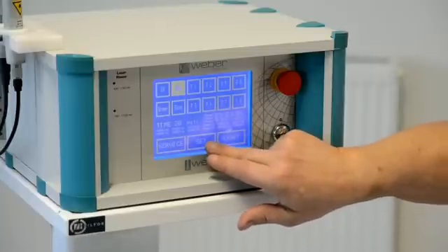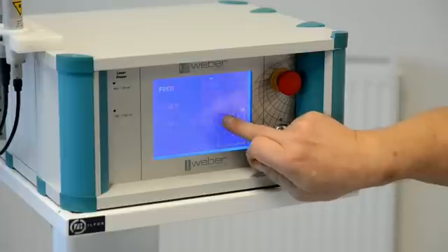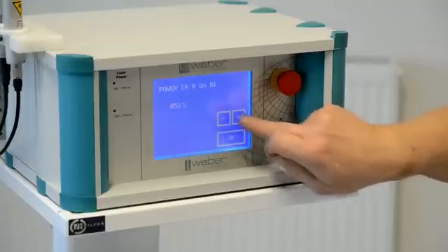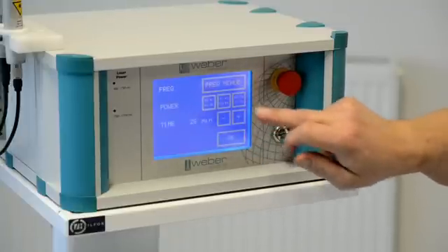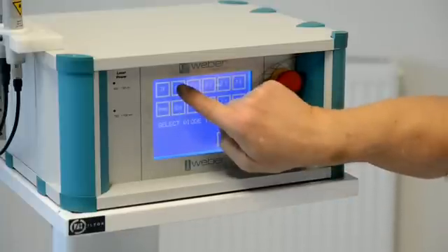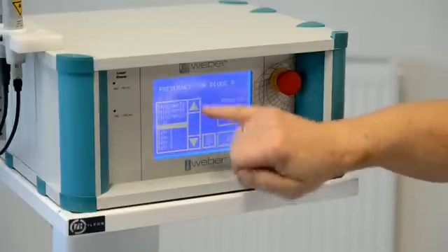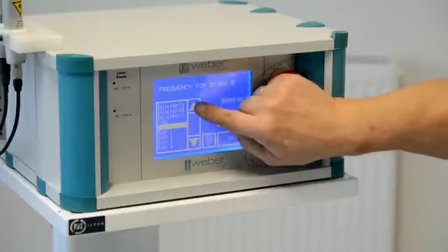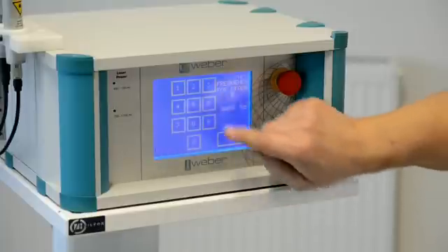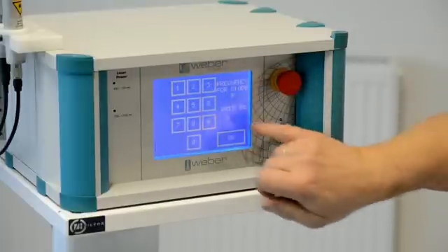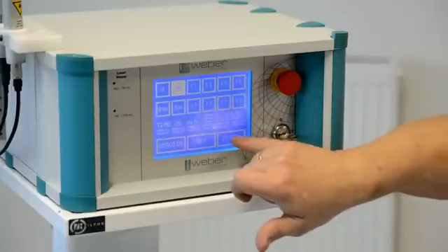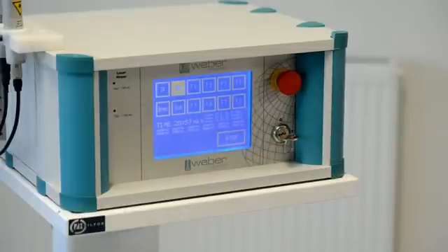If I want to change something, I go in the set mode, and I can vary treatment time, and I can vary the power of each laser. In the frequency mode, I press frequency, I choose one of my lasers, here the red laser, and you see on the display it is now in the CW, so in the continuous wave mode. If I want to add a free frequency, I go to free, I give in a frequency with my choice, maybe 15 Hz in this case, press OK, I confirm the data, no other frequencies, now I confirm time and power, and now I press the red laser, and it will run in the 15 Hz frequency mode.